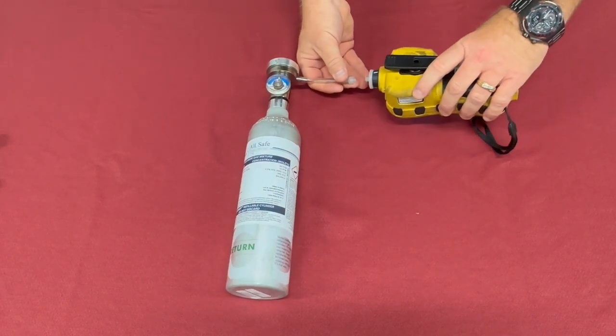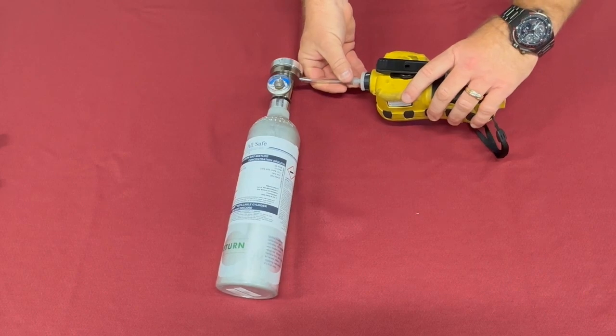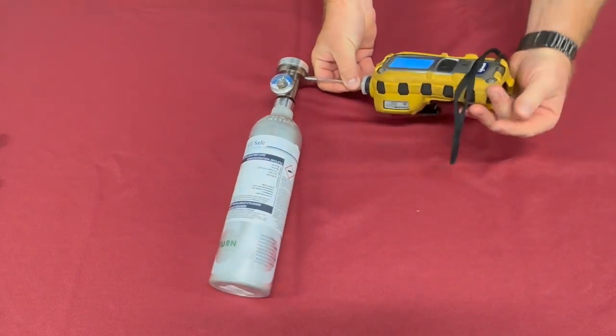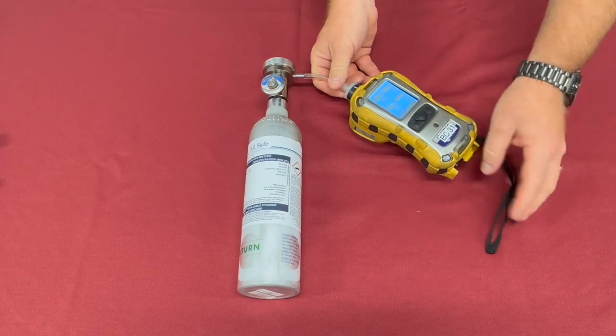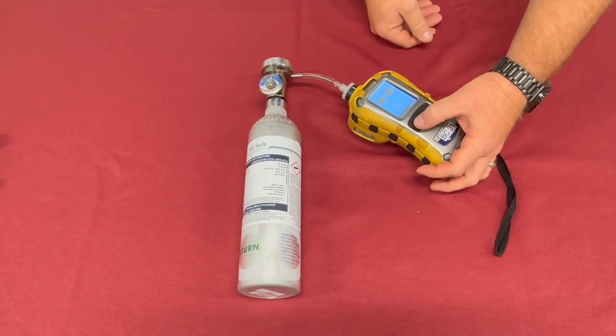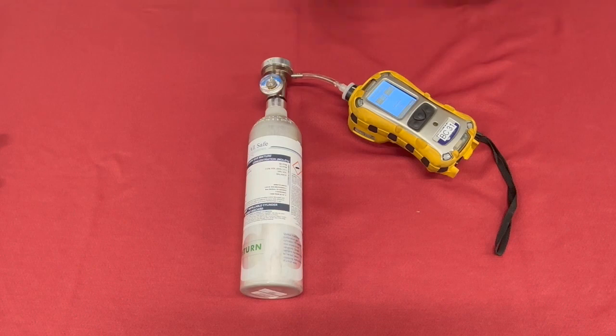So the easiest way to do this is turn the meter upside down, connect, and rotate. That way you can see the meter during the test. Then hit start. This first calibration lasts 240 seconds. The reason for this is one of the sensors involved is the hydrogen cyanide sensor. Hydrogen cyanide sensor is what's known as a long soak sensor. It takes an extremely long time for this sensor to respond to the hydrogen cyanide gas.